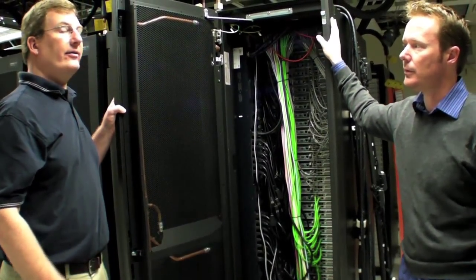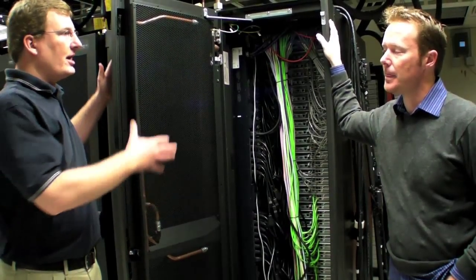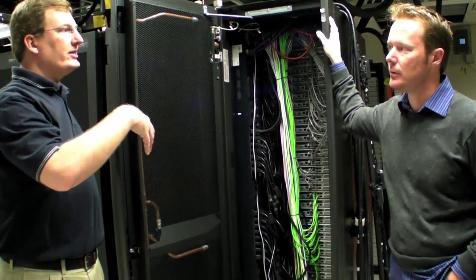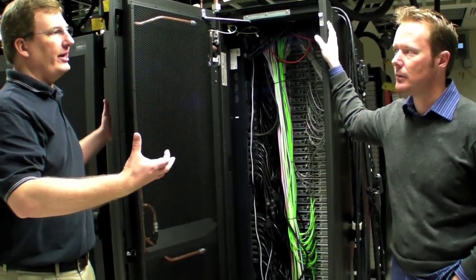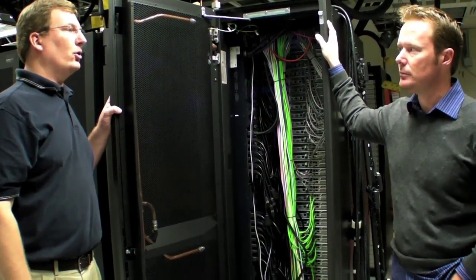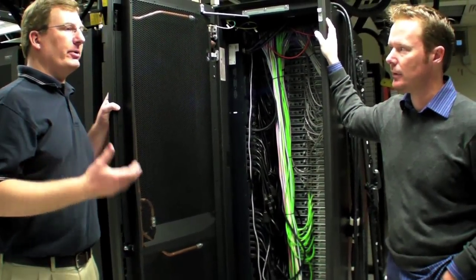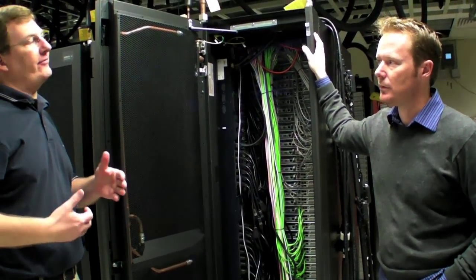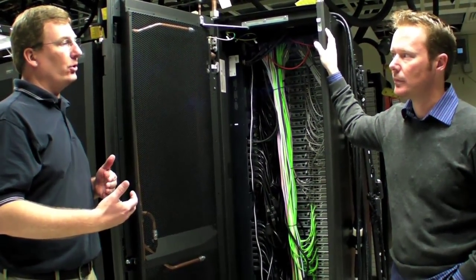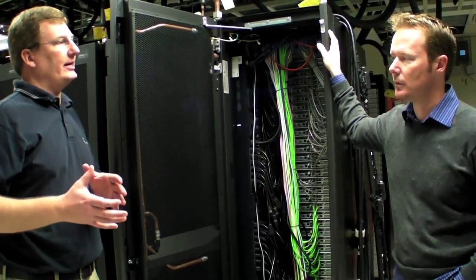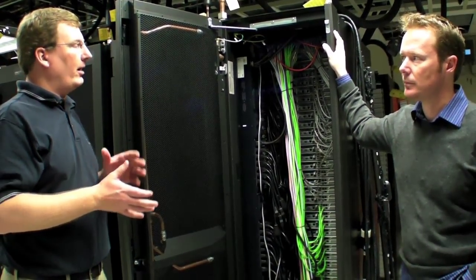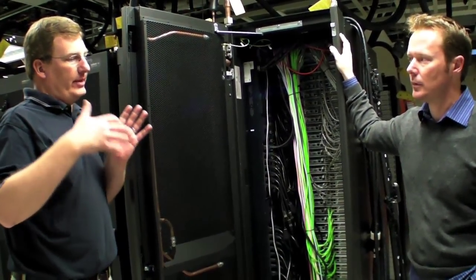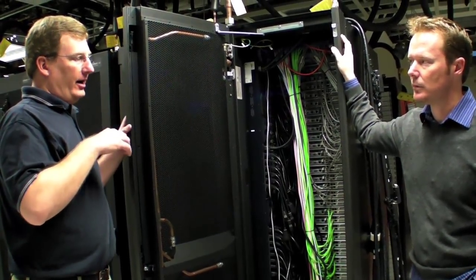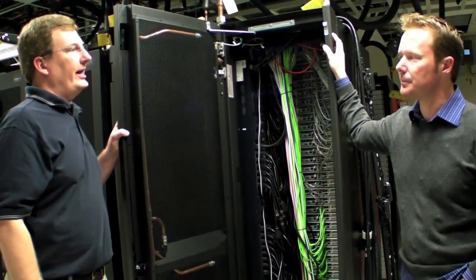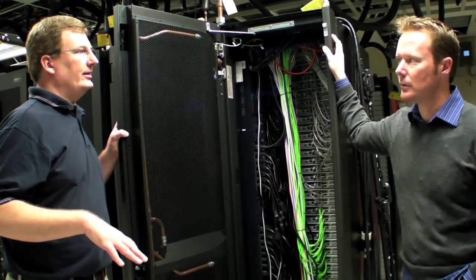You also have added flexibility because the air all around that space is basically room temperature. I don't have to be in a hot aisle, cold aisle configuration, so for data centers that are older and haven't fully gone to that configuration yet, but are starting to get new, higher power servers, this is a solution for them. They can use this to control the temperature in that environment without doing anything additional.